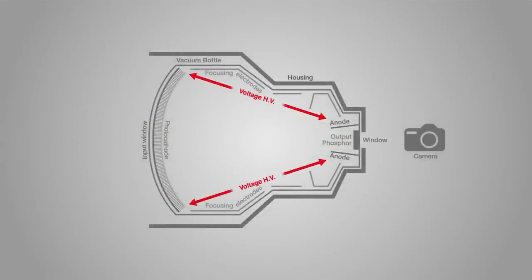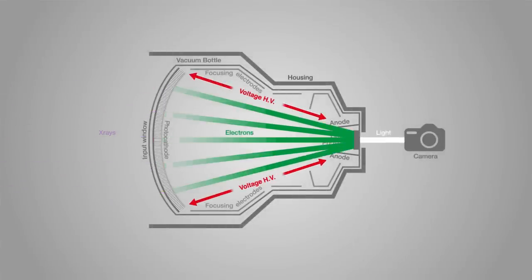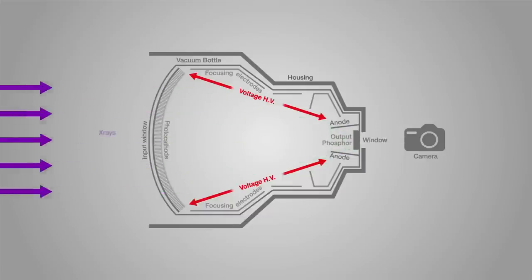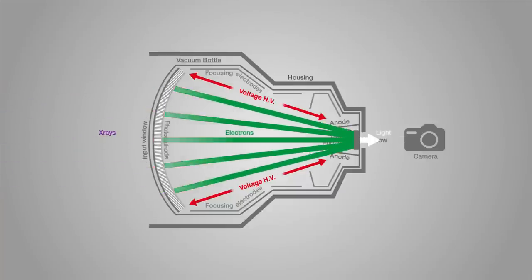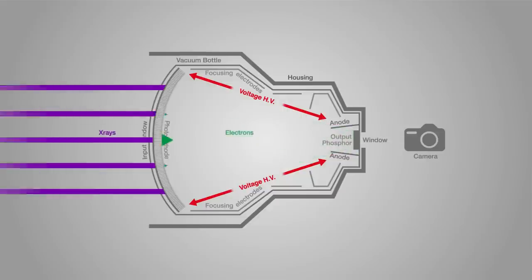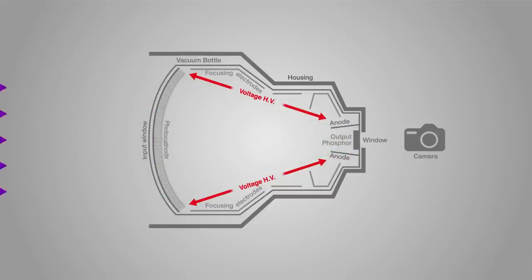The benefit of the image intensifier is that the signal intensity of the X-ray beam can be amplified through the selection of scintillator, the magnitude of the high voltage, and the nature of the focusing components which control the electron stream, and then the sensitivity of the phosphor screen and of the image capture device, which are now operating at visible light frequencies.